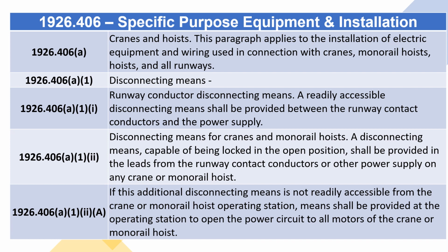1926.406(a)(1)(ii) Disconnecting means for cranes and monorail hoists. A disconnecting means, capable of being locked in the open position, shall be provided in the leads from the runway contact conductors or other power supply on any crane or monorail hoist. If this additional disconnecting means is not readily accessible from the crane or monorail hoist operating station, means shall be provided at the operating station to open the power circuit to all motors of the crane or monorail hoist.